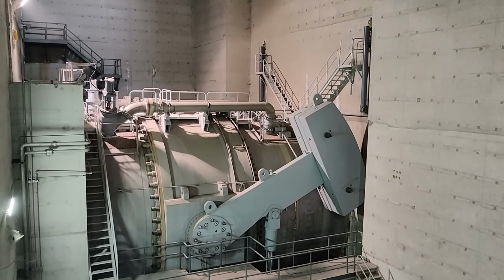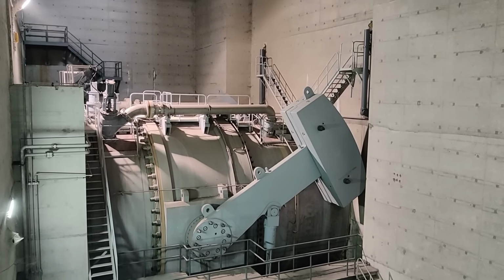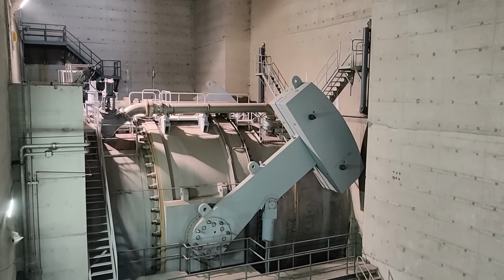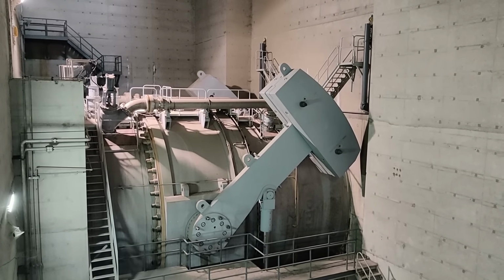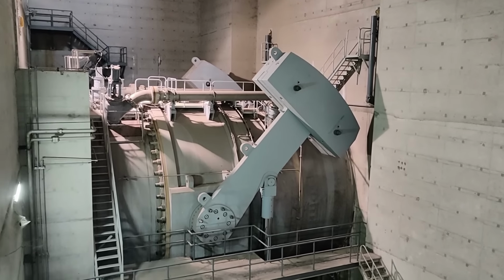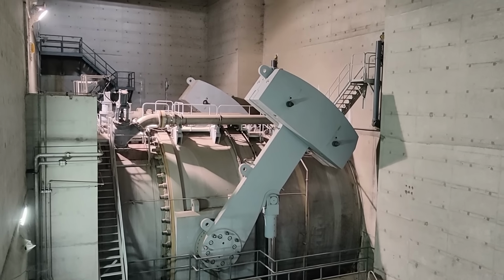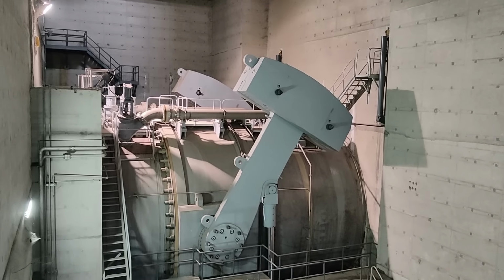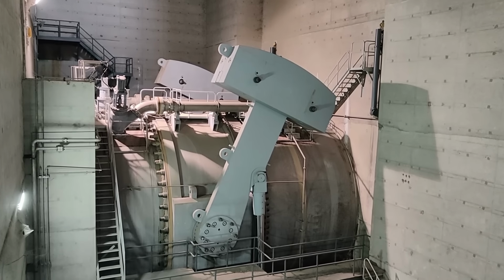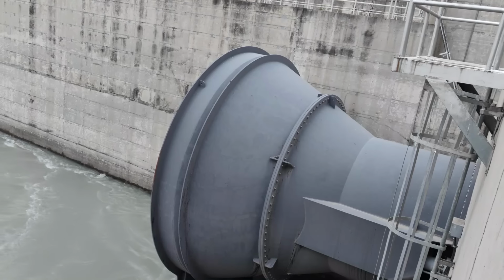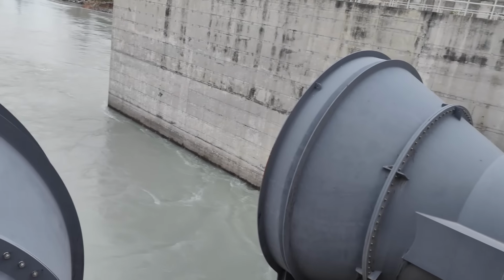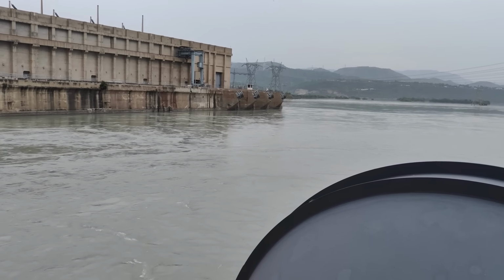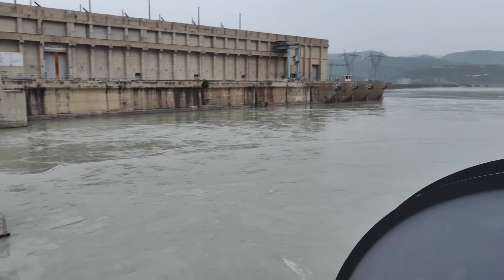At this point, water is now available inside the turbine spiral casing, but the turbine still isn't rotating because the wicket gate remains nearly closed. So hydraulically the unit is prepared, but mechanically it is still restrained. Then come steps number 4 and 5, pressure relief and safety verification.